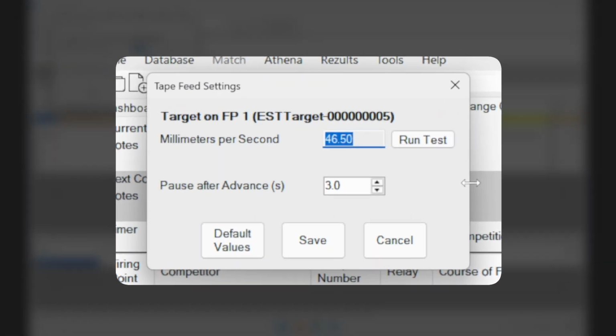In the Tape Feed Settings dialog box, you will see the default settings for the tape feed. Millimeters per second. This is the speed of the tape feed motor, measured in millimeters of tape advance per second. By default this is 15 millimeters per second. Pause after advance. This shows the amount of time, in seconds, the scoring algorithm will pause after the tape feed advances. By default, this has a 3-second value. We'll cover this topic in a little more detail shortly.